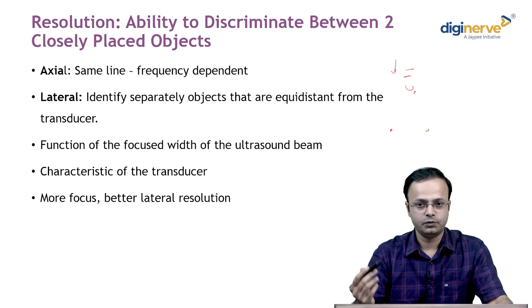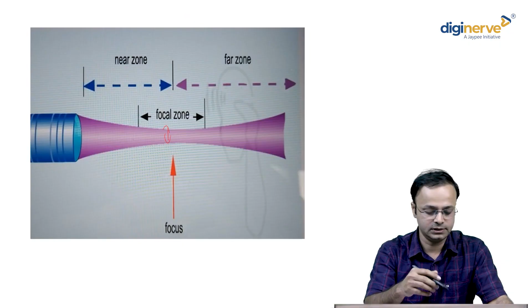Resolution depends upon the focused width of the ultrasound beam. So this is the transducer and this is the focused width. If you want to identify two objects which are very close to each other, you should decrease the focal zone as it becomes narrow. We will have more information regarding the lateral resolution.